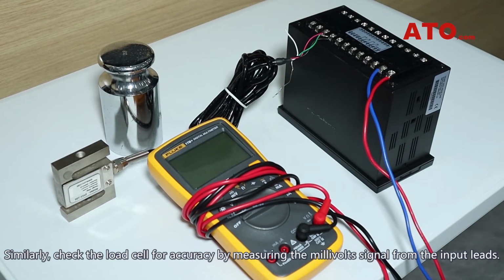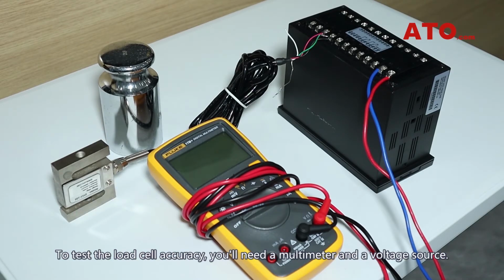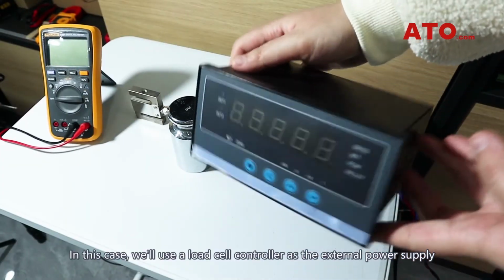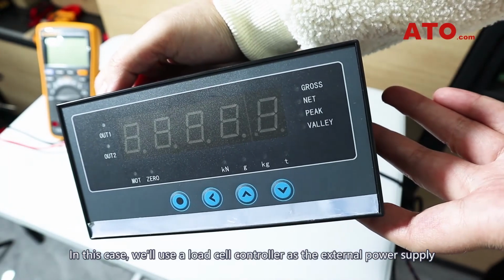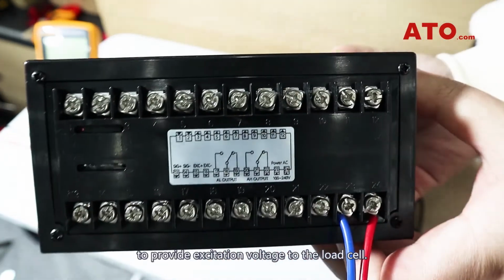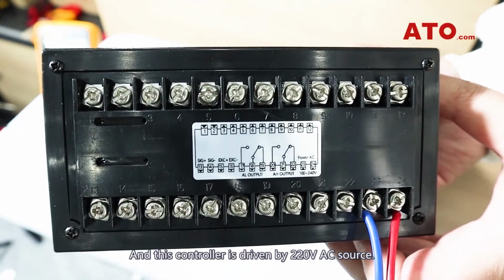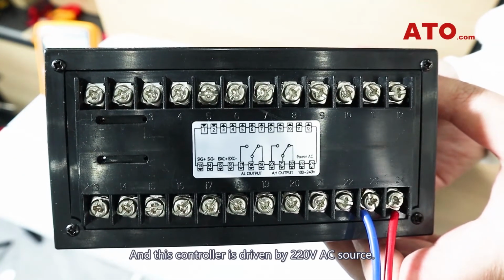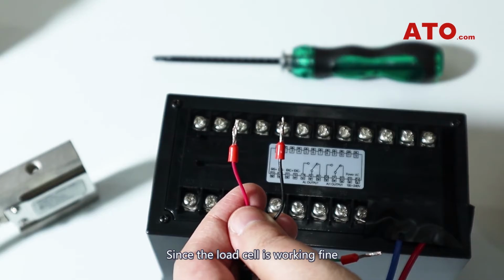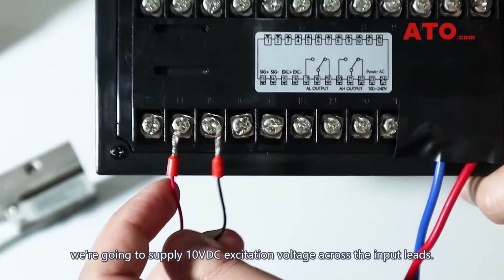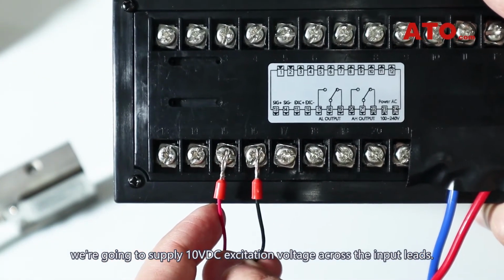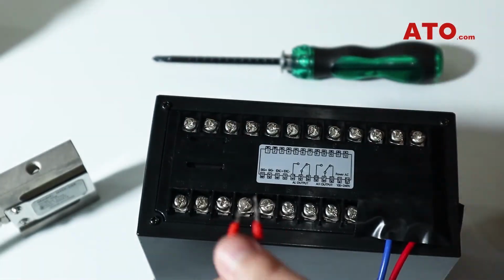Similarly, check the load cell for accuracy by measuring the millivolt signal from the input leads. To test the load cell accuracy, you'll need a multimeter and a voltage source. In this case, we'll use a load cell controller as the external power supply to provide excitation voltage to the load cell, and this controller is driven by 220 volts AC source. Since the load cell is working fine, we're going to supply 10 volts DC excitation voltage across the input leads.